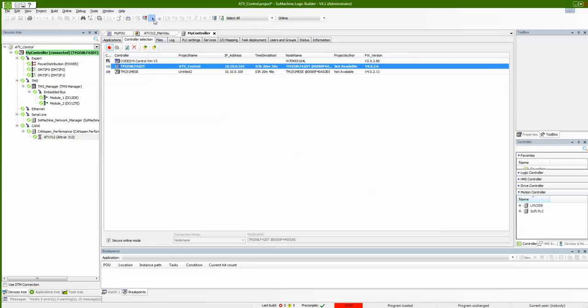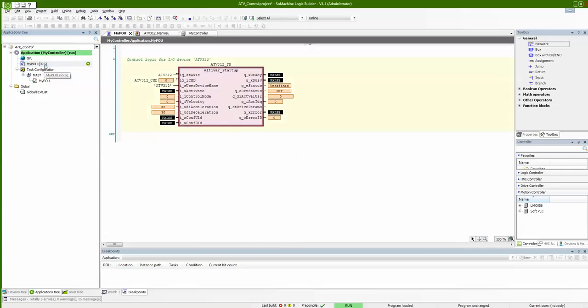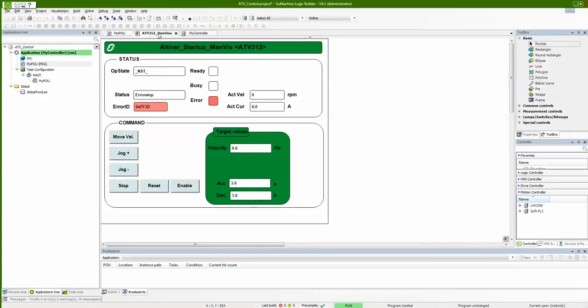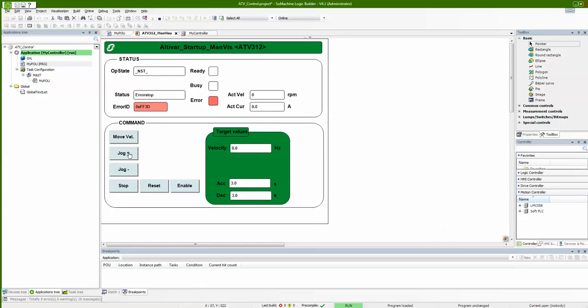Now I just need to start my PLC to execute my code. The PLC is now in run. I go to my application tree, open my code, and I can see it online. The command word is zero, so there's no active command yet. I switch to my visualization and I can see the current state is 'error stop' with an error code shown. Actual velocity is zero, actual current is zero. I can trigger commands using the buttons and give velocity reference and acceleration/deceleration reference by entering values.